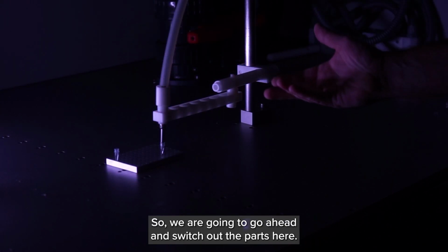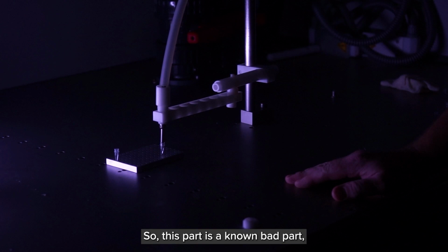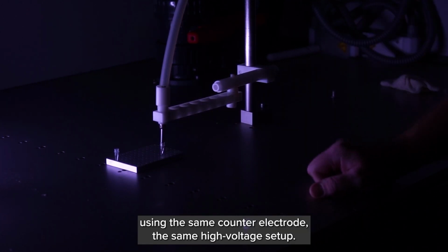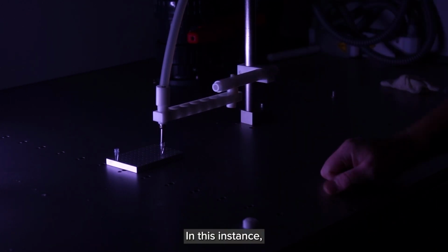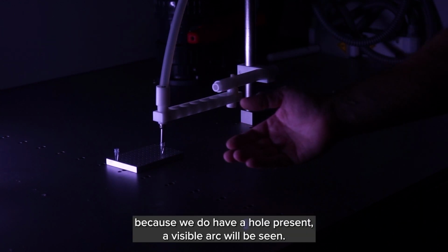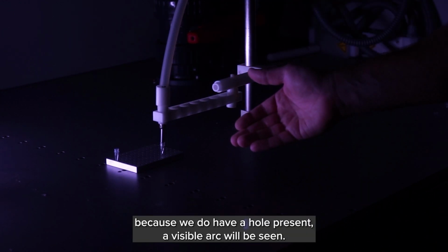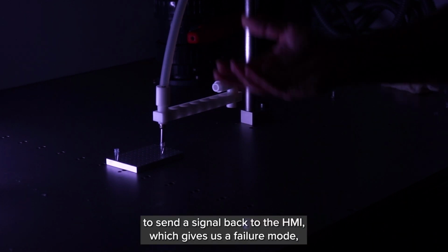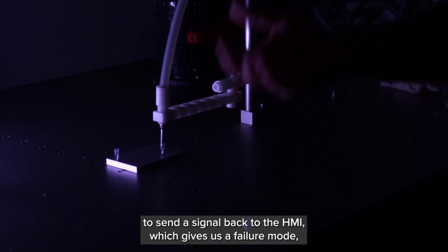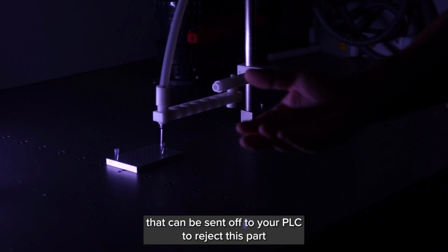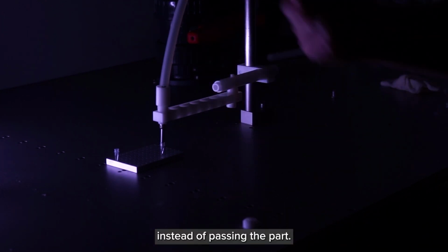So we've gone ahead and switched out the parts here. So this part is a known bad part using the same counter electrode, same high voltage setup. In this instance, because we do have a hole present, a visible arc will be seen. That will allow us to send a signal back to the HMI, which gives us a fail mode that can be sent off to your PLC to reject this part instead of passing the part.